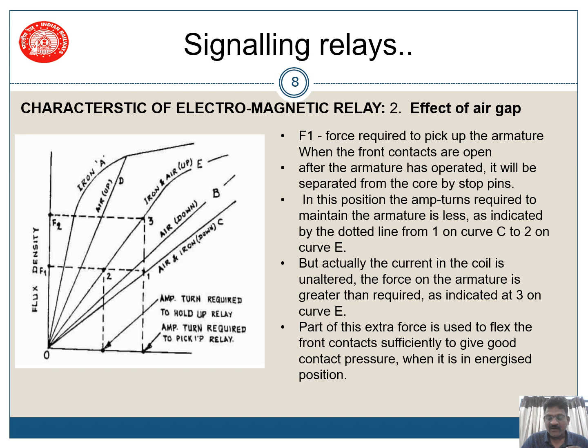But we are not reducing the current of the coil. That is, the current is not reduced. So here you can see this is the point 3, that is the current available when the relay is in picked up condition. This extra current helps the relay in getting the contacts more pressure. The contact pressure is increased because of this excess current that we are giving to the coil. Though this much current is enough, we are giving F2 up to 3 when the relay is in picked up condition. This is the effect of air gap, which requires excess pressure to hold the contact properly.